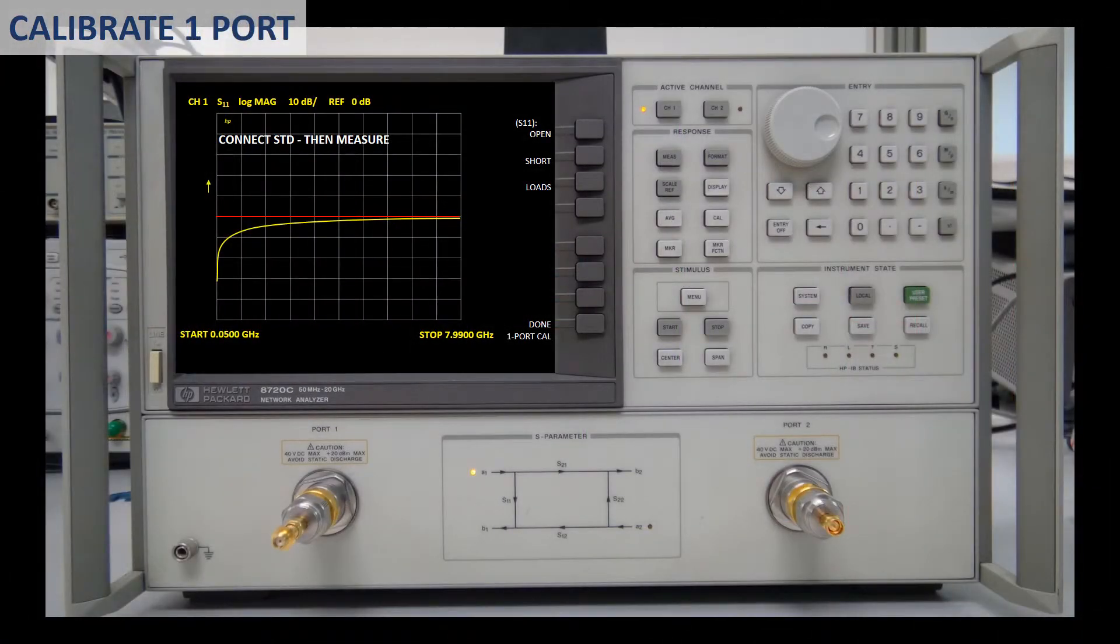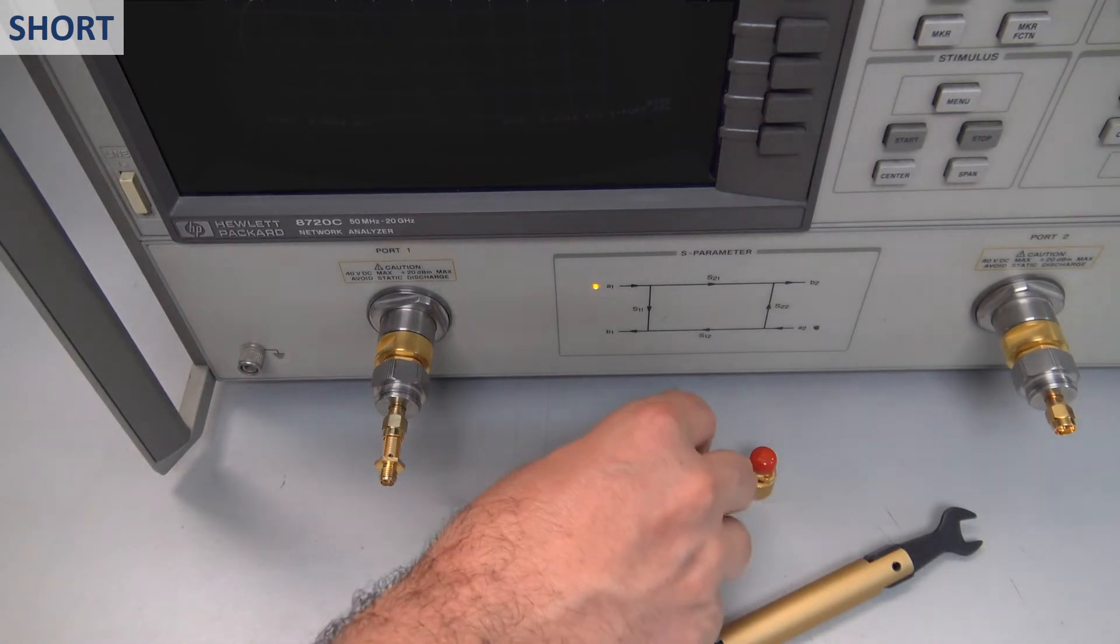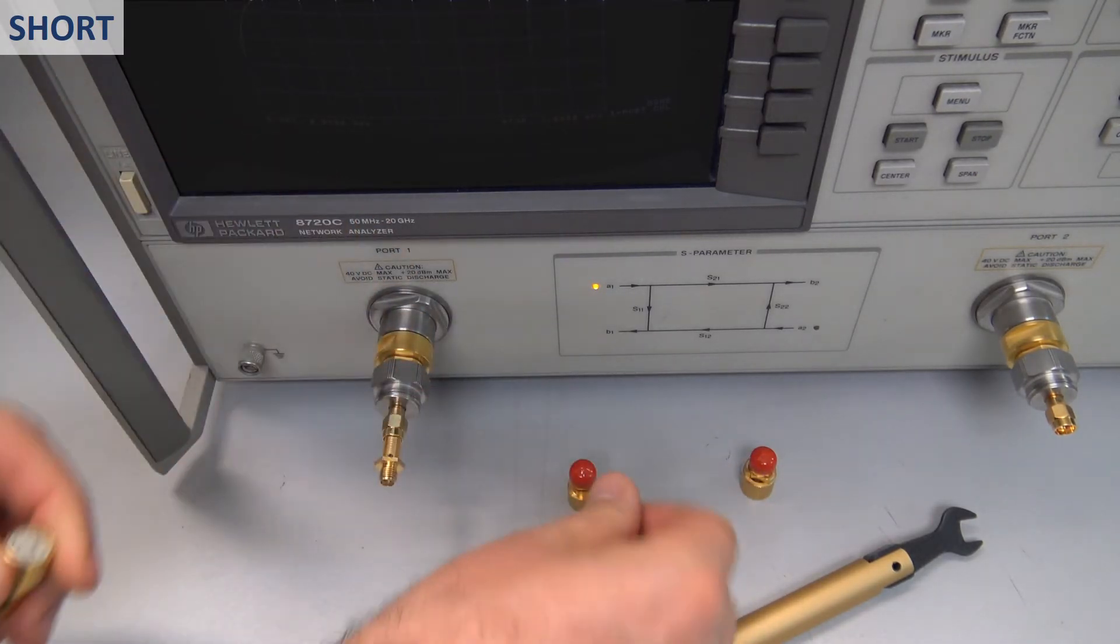The network analyzer displays a message asking us to connect the standards. The calibration kit contains three different standards: a short circuit, an open circuit, and a matched load. Therefore, we need to do three measurements. We don't need to follow any particular sequence. Let us start with the short.